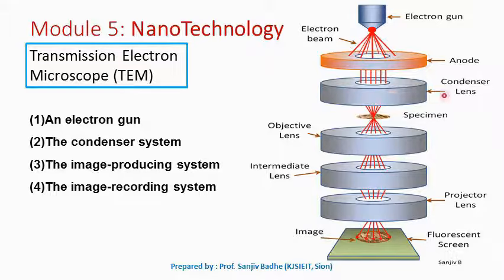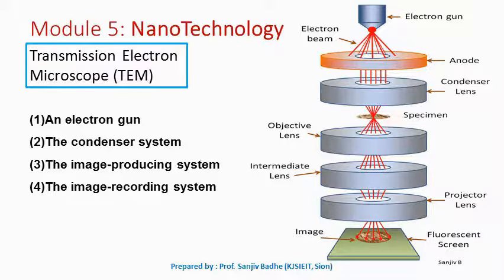We have a condenser system which contains a condenser lens. A magnetic lens is used for condensing — that is, focusing — the electron beam onto the sample. The condenser lens focuses the electron beam onto the specimen, the object which is to be viewed. The intensity and angular aperture of the beam is controlled by the condenser lens system, which is kept between the anode and the specimen.